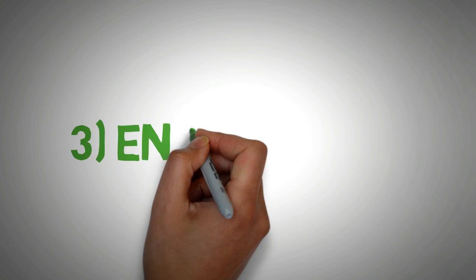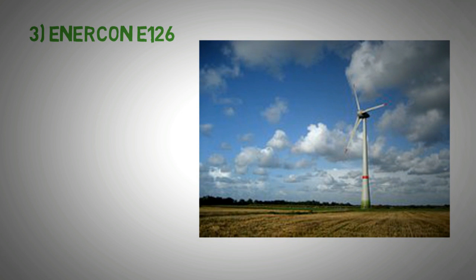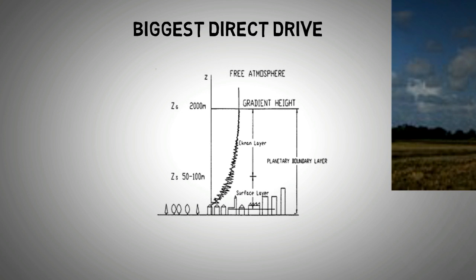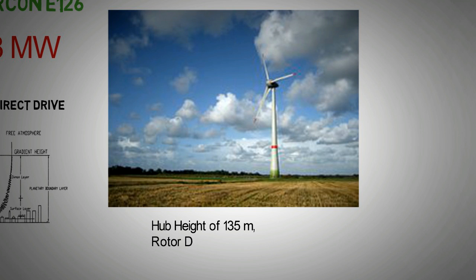At number 3 we have the Enercon E126. The Enercon E126 is a turbine that can generate up to 7.58 megawatts. At the time of its launch it was the biggest wind turbine in the world, and it is still the biggest direct drive turbine in the world. Direct drive means that there is no gearbox in the design. What makes this turbine unique is that it has a very high hub height with relatively shorter blades. The idea is that the turbine would capture wind at a higher elevation where the quality of wind is much better. The turbine has a hub height of 135 meters, a rotor diameter of 127 meters, and a total height of 198 meters.